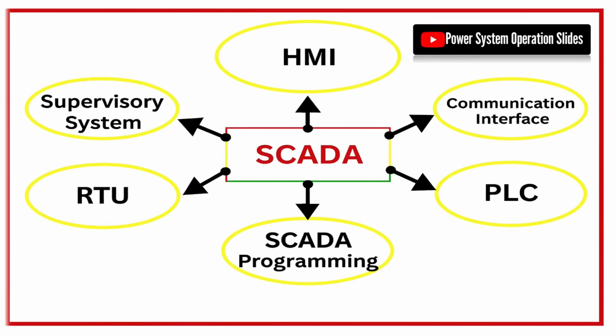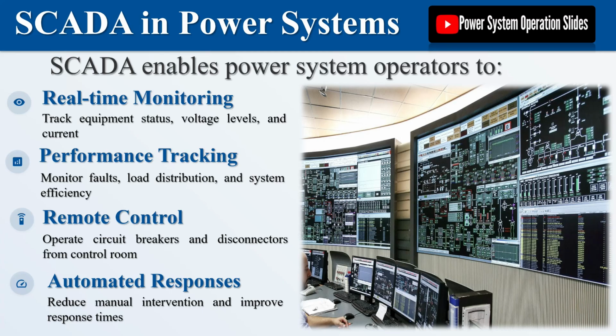In a power system context, SCADA serves as the central nervous system, continuously monitoring the health and performance of equipment such as circuit breakers, transformers, and feeders. It provides operators with the ability to remotely control operations like opening or closing circuit breakers and disconnectors, which dramatically improves operational efficiency and safety.